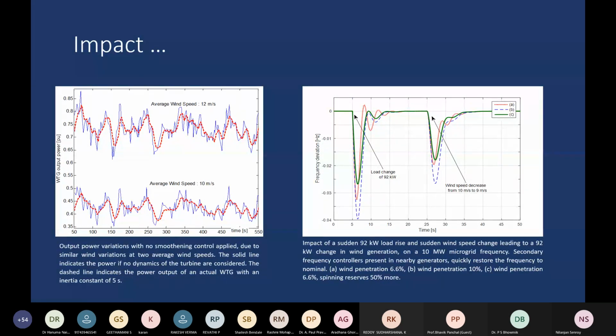Also, this graph on the right shows what happens if you have a 92 kilowatt load rise. So at 5 seconds, the load increases in a small microgrid. The load has increased by 92 kilowatts. And at 25 seconds, the wind has dropped, and that drop in the wind causes a similar 92 kilowatt change in the generation. So basically, the same kind of event has occurred, which is that a generation load mismatch of 92 kilowatts has occurred at 5 seconds and at 25 seconds. The first event is more severe because it is a load change event.